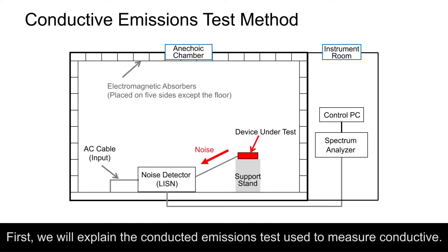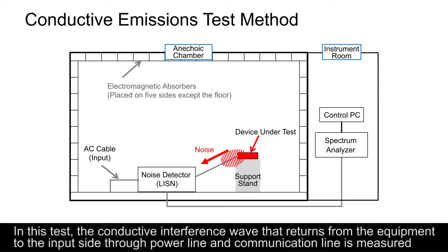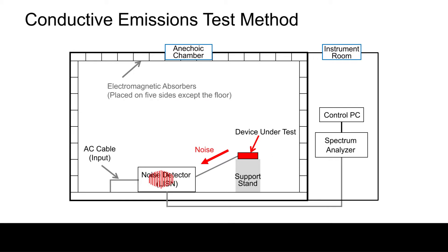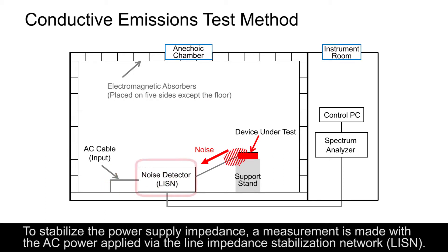First, we will explain the conductive emission test used to measure conductive emission. In this test, the conductive interference wave that returns from the equipment to the input side through the power line and communication line is measured to make sure that the interference wave does not exceed the limit. To stabilize the power supply impedance, a measurement is made with the AC power applied via the line impedance stabilization network.